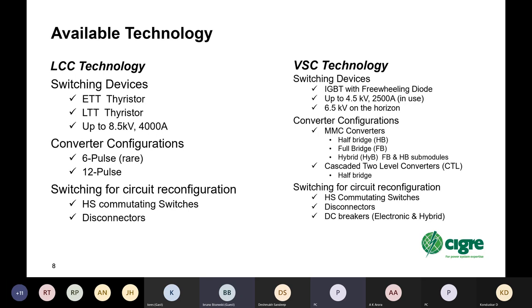up to 4.5 kV and 2500 amps in use. 6.5 kV is on the horizon. I think GE is now using 6.5 kV IGBTs. Converter configurations, MMC, primarily the technology now in use, and they can be configured as half bridge converters, full bridge converters, or hybrid converters, which have both half bridge and full bridge modules in the valve arms.